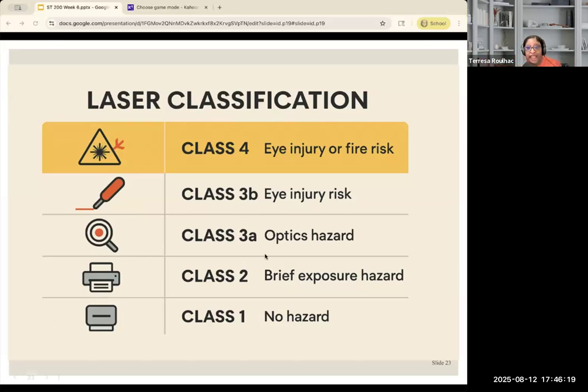With class 3A, they normally do not cause eye injury if viewed, but they present a hazard if viewed with collecting optics, or if you have a fiber optic cable, or you're looking through something like a laparoscopic case—it could cause damage that way.